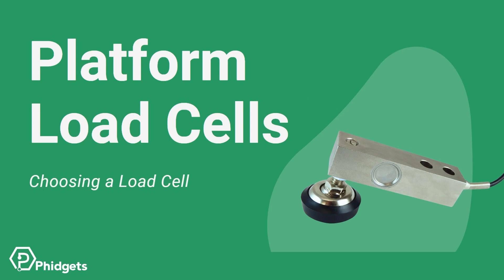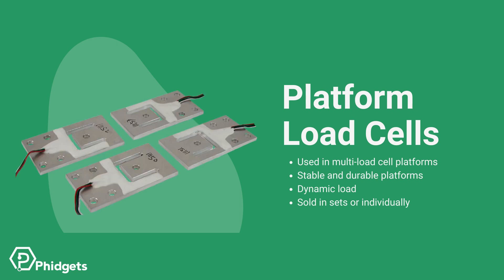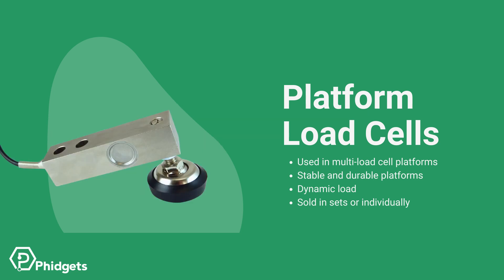Platform load cells are designed to be used in parallel for multi-point weighing platforms. Because the platform is supported in more than one place, systems made with these load cells are very stable and durable. Load distribution does not matter, and dynamic forces can be easily withstood. Some platform load cells are sold in sets, indicating they should only be used together, while others are sold individually, meaning they can be used in parallel with any number of the same load cells.